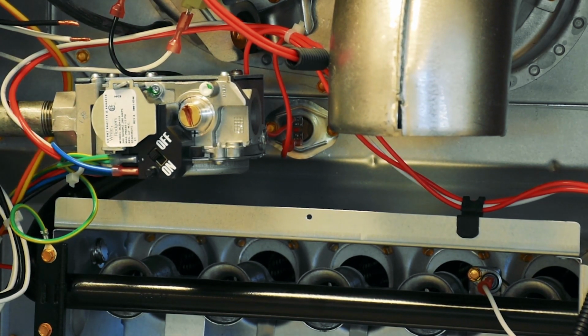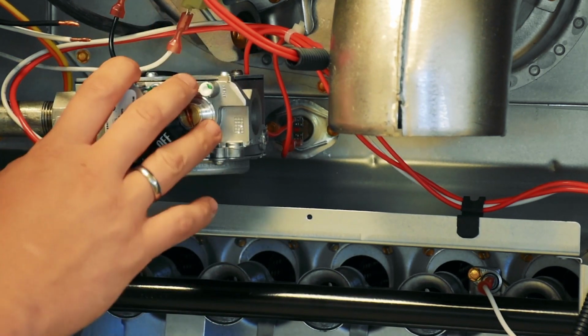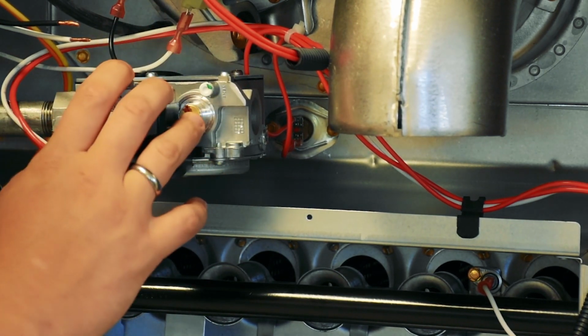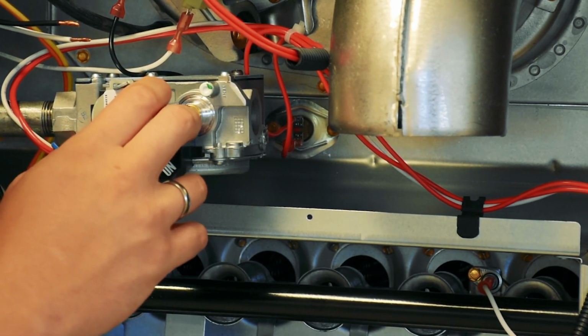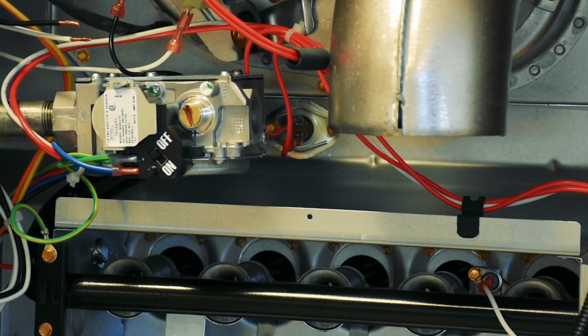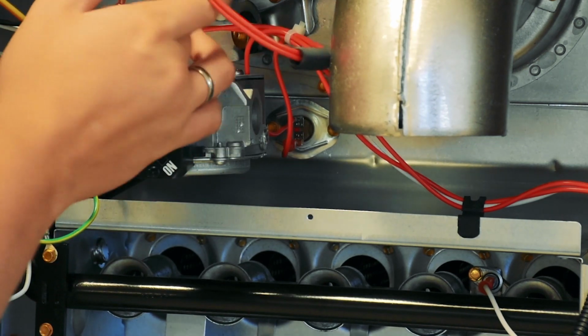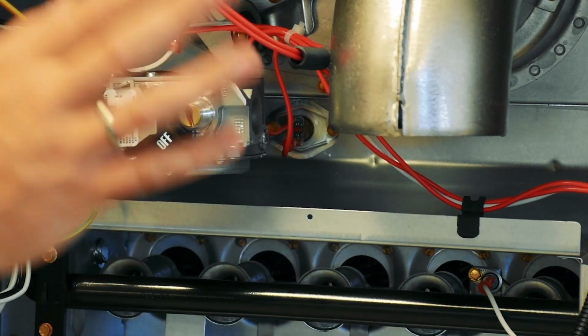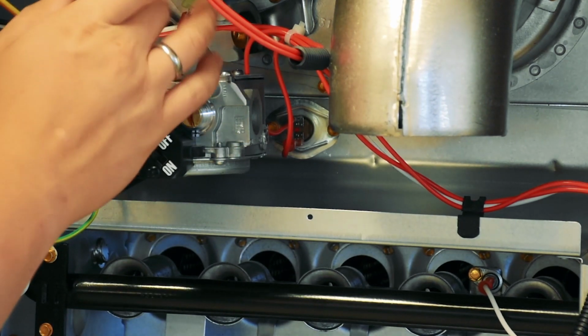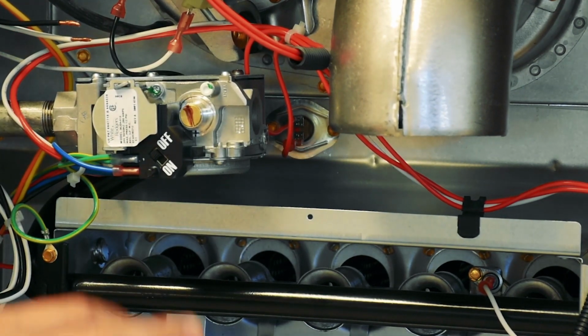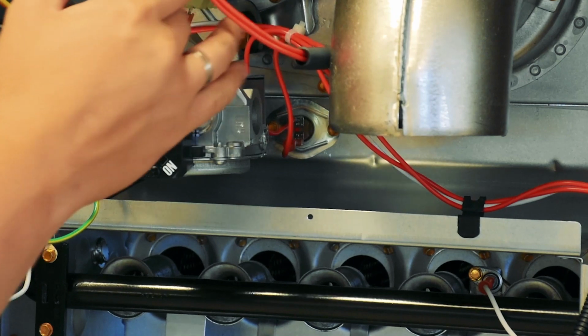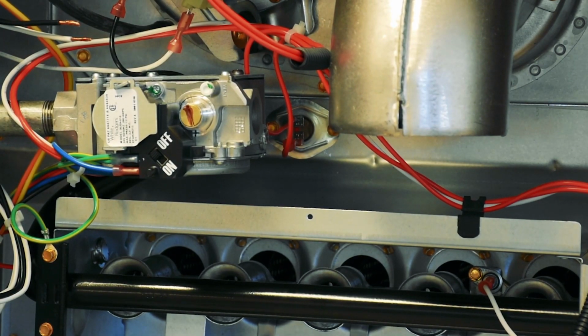What will happen? It will shut down the power to the gas valve, because here is the 24 volts actually. Then, sometimes it shuts down this inducer motor immediately, but normally it should run a little bit, probably 10-15 seconds, and then shut off the inducer motor too.